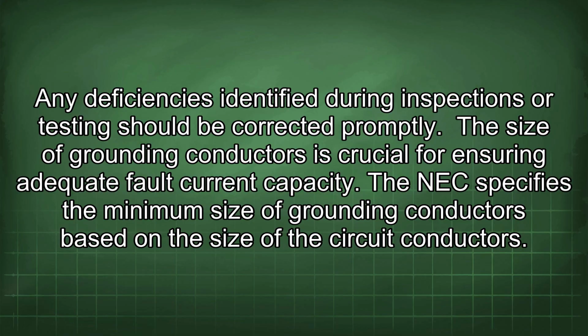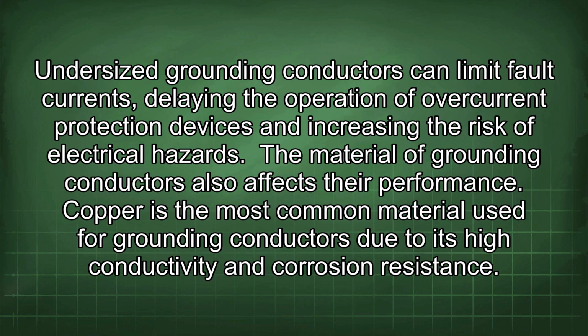The size of grounding conductors is crucial for ensuring adequate fault current capacity. The NEC specifies the minimum size of grounding conductors based on the size of the circuit conductors. Undersized grounding conductors can limit fault currents, delaying the operation of overcurrent protection devices and increasing the risk of electrical hazards. The material of grounding conductors also affects their performance.